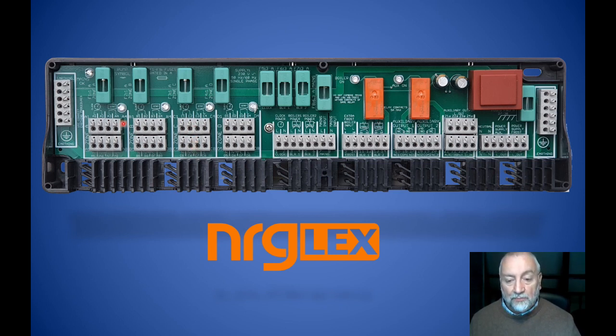But the 4th terminal here, if power ever arrives, having left the clock, gone off out to your cylinder stat or room stat, come back from the cylinder stat or room stat and arrives here, 3 things happen. This light lights. The fourth terminal is joined to the fifth and sixth terminal. So if you have a pump connected to there or a motorized valve, the valve will open or the pump will run or whatever. And then, as well as that, through an electronic process, this relay will close. So the only terminal you ever have to learn that really matters is the fourth one here, here and here in A, B, C and D, because they're the ones that do all the work.